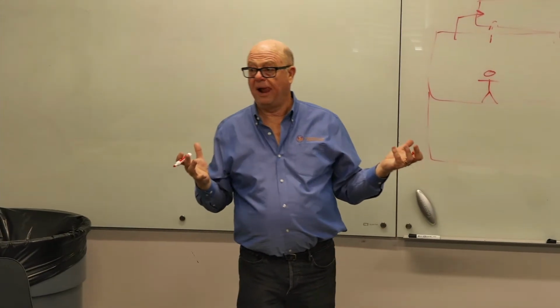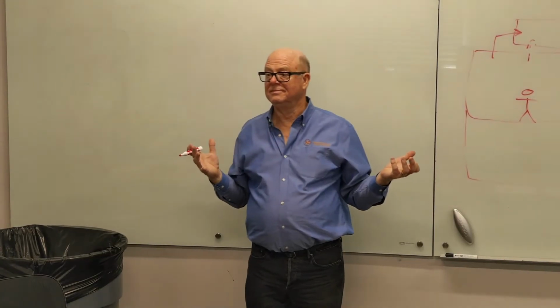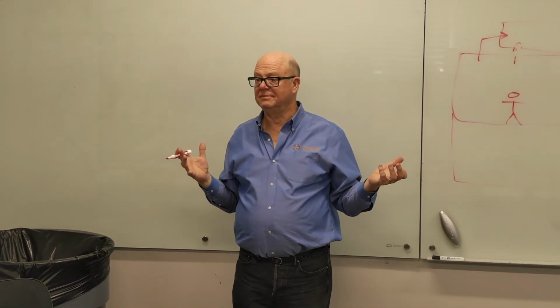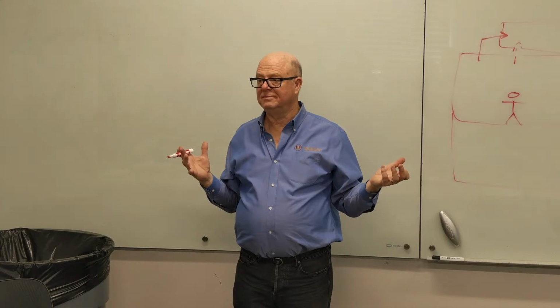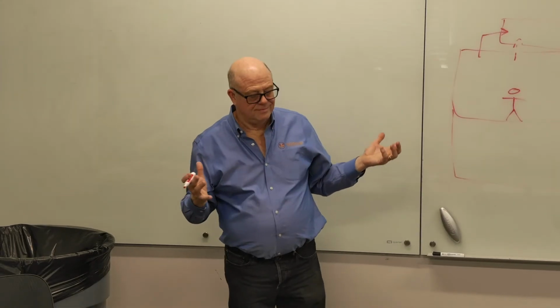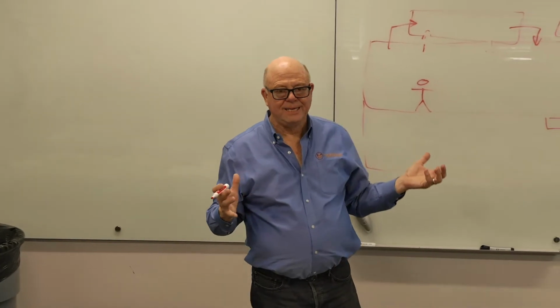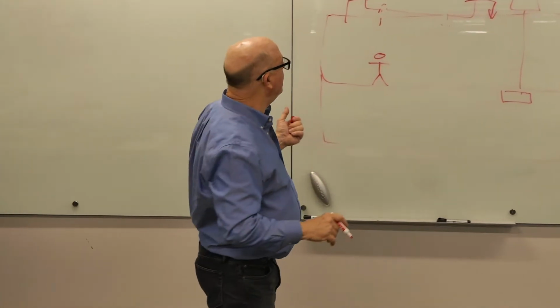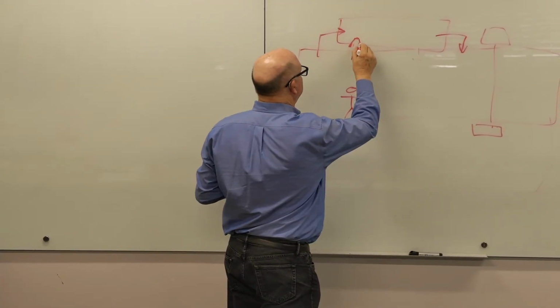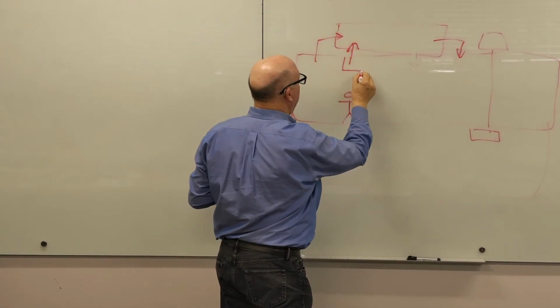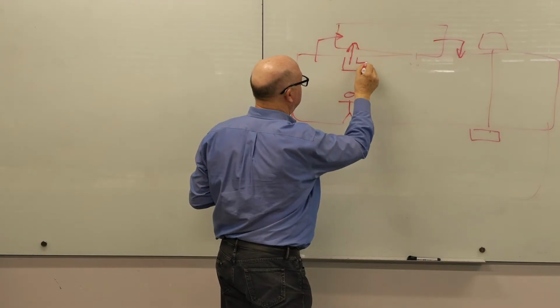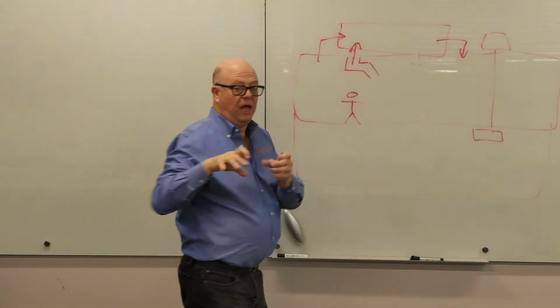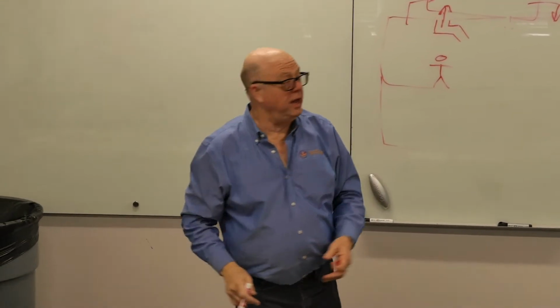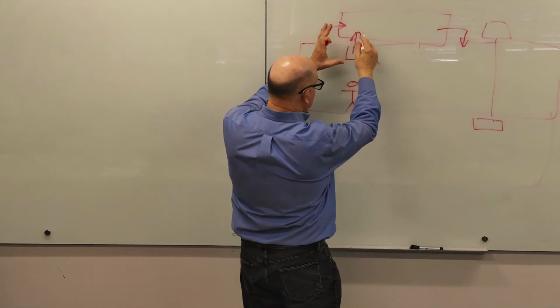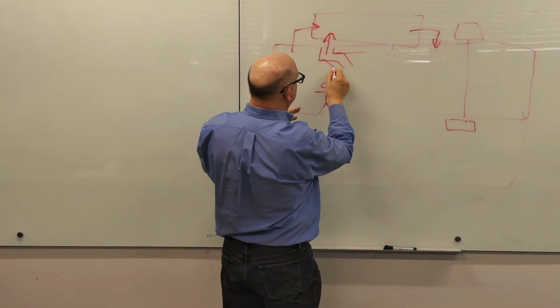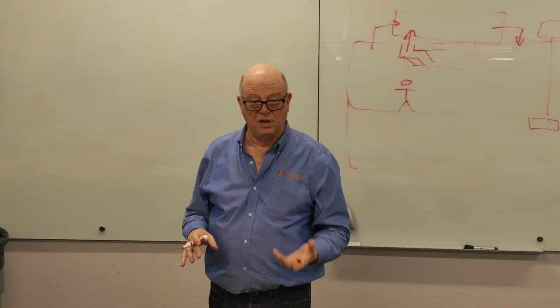Can I ask how have you typically seen those configured? Is it just a straight duct plugged into the ceiling, or did they put an elbow on it? Is it sized at 500 feet a minute? Did you put 2 elbows on it? Sound doesn't like going around right-hand corners. Good point. There's ways to defeat that. So if you're going to do this, you could come down, you could have a duct with a couple of L's, and it could be lined, and once you were down out of the initial opening, you could make this bigger and cut down on the velocity.